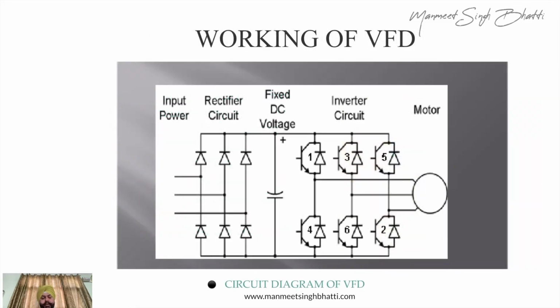Now, as I have already explained, this is a consolidated diagram of the complete VFD operation. In the beginning, on the left side, if you see, the three-phase power is coming. The three-phase power is converted to DC. It's a bridge wave rectifier. It converts the complete power to DC. From the DC, then you have a capacitor in between. The job of this is to smoothen the curve.